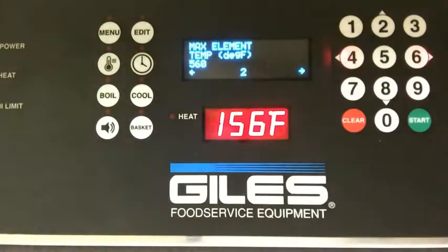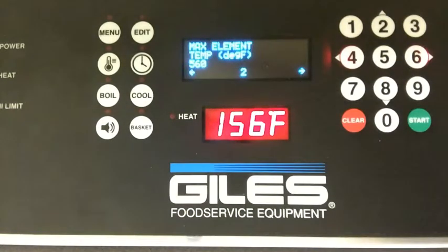Number 2, the maximum element temp. This one's set to 560 degrees. We have one probe in there that is tied directly to the heat element. If that heat element exceeds 560 degrees, we can safely assume that there is no oil in there. It's an extra safety, and it will shut the heat elements off.